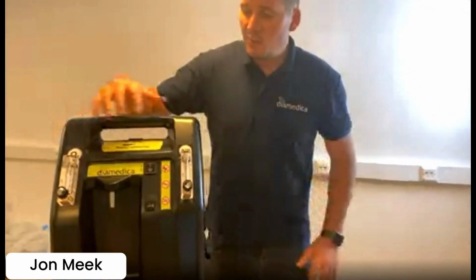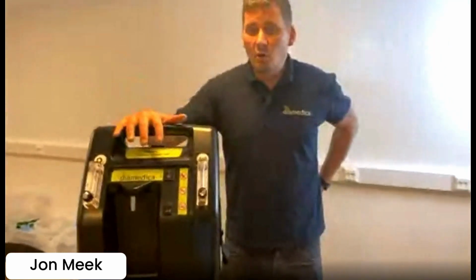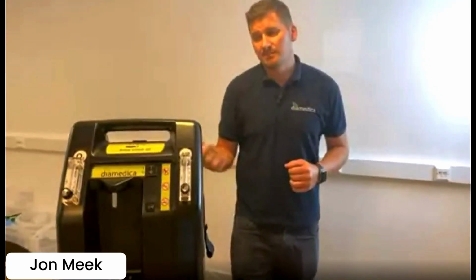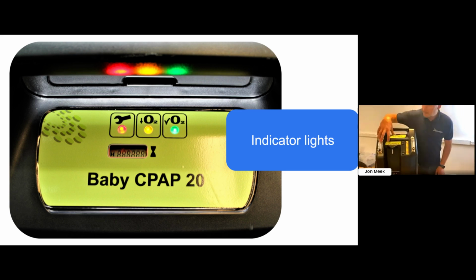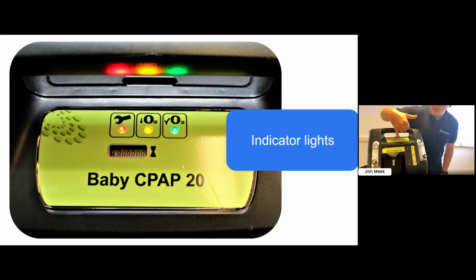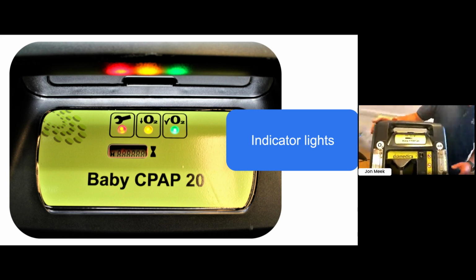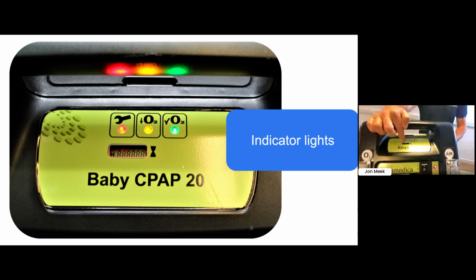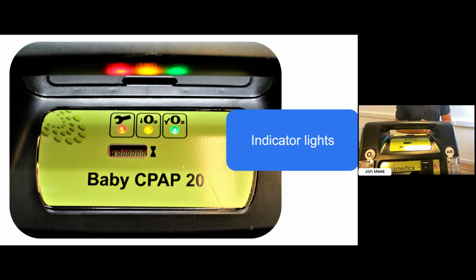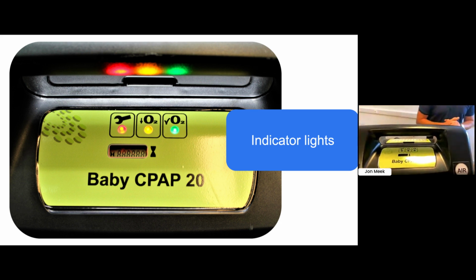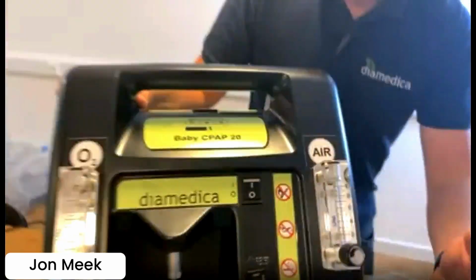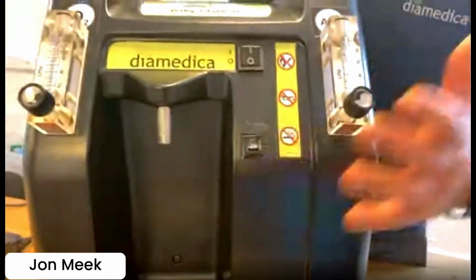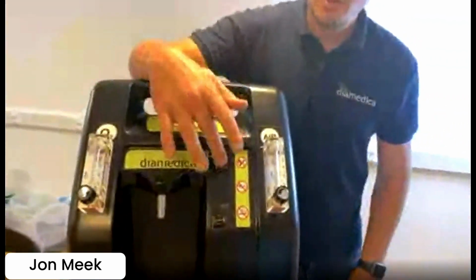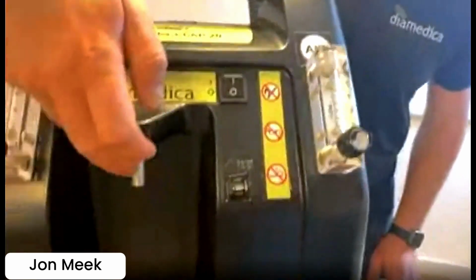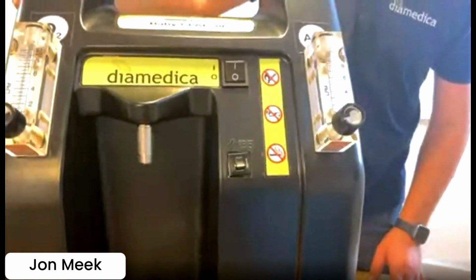On these, they have their own built-in alarms, built-in oxygen lights and everything. They have their own self-test, which is really important. On the front here, we have a maintenance alarm, a low oxygen light, and a green oxygen light, so it tells you when everything's good. We have an hours counter for maintenance, but also for how many hours it's run. We have a circuit breaker for any power fluctuations, an on-off switch, and a common gas outlet for the oxygen and air, which we connect onto it.